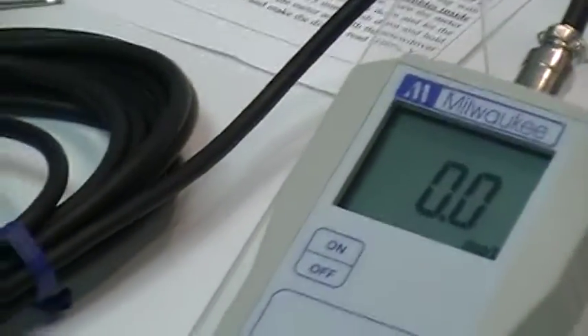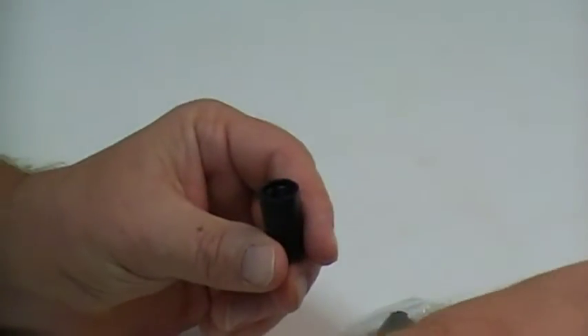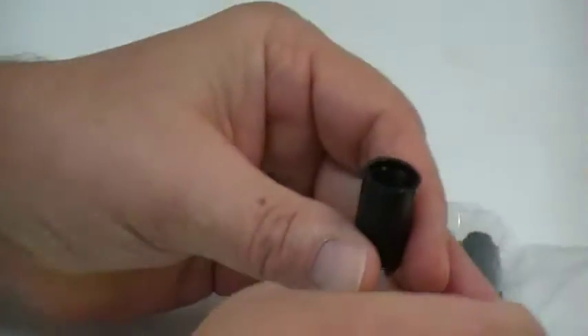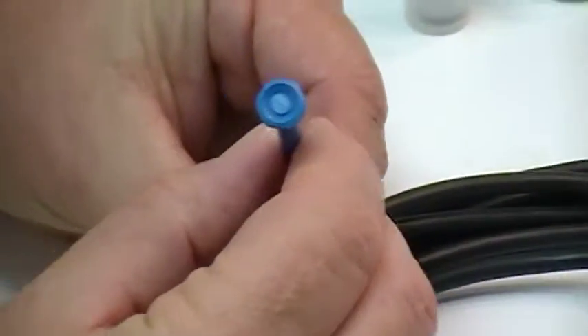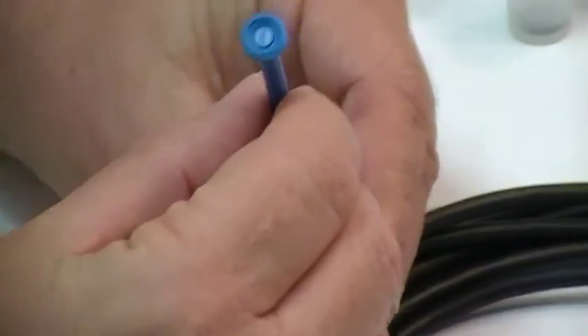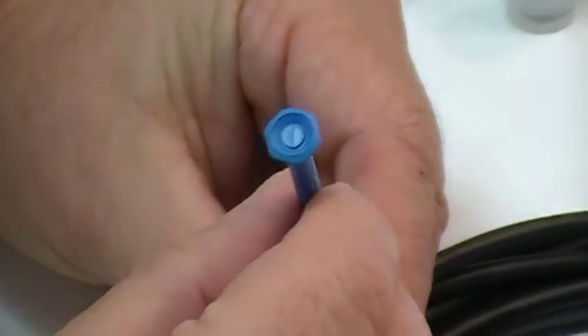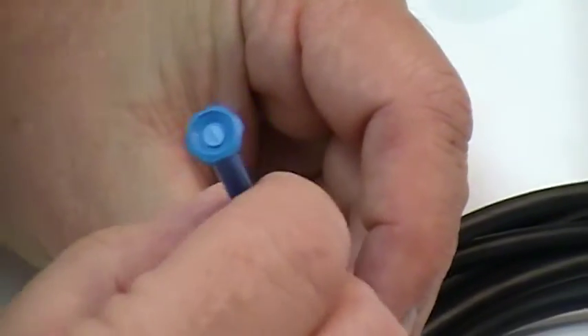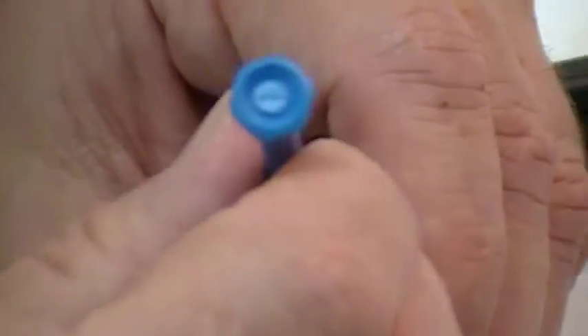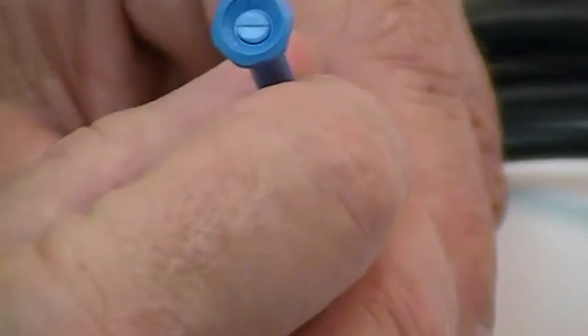Next, you will take your membrane. You want to select an O-ring that came in the protective cap. Put the O-ring into the membrane, and with the screwdriver tap it down onto the shoulder at the bottom of the threads. Now this is black on black, so it's difficult to see the O-ring inside the membrane, but there is a shoulder at the bottom of the threads.